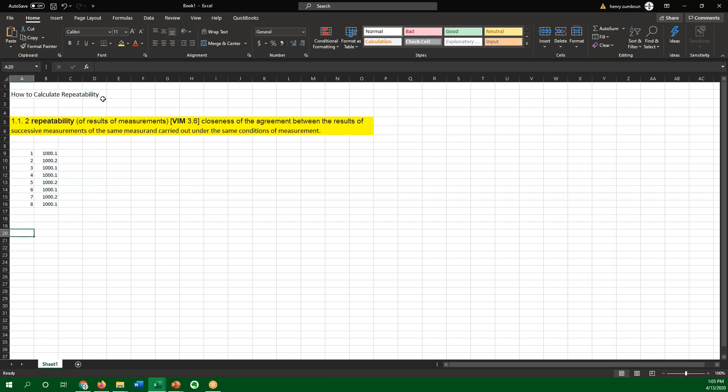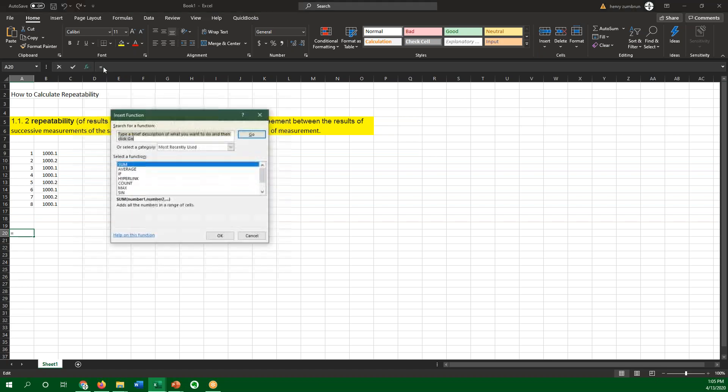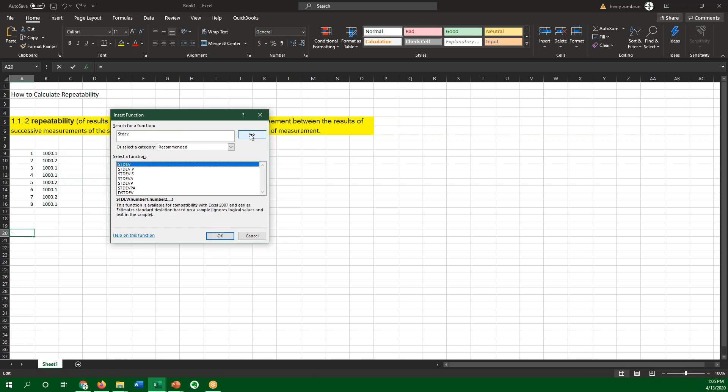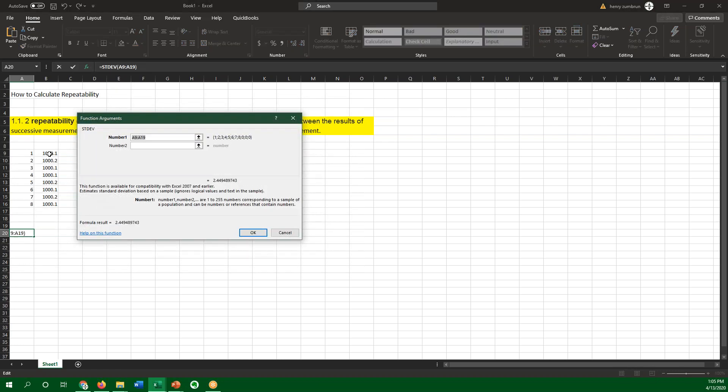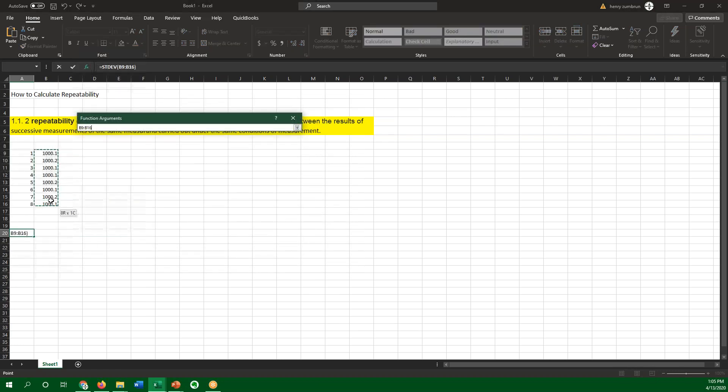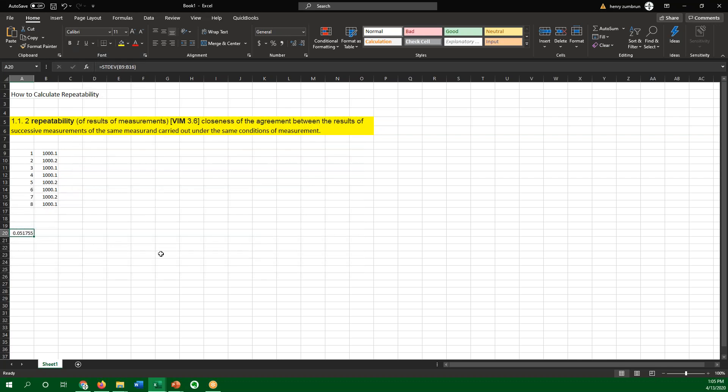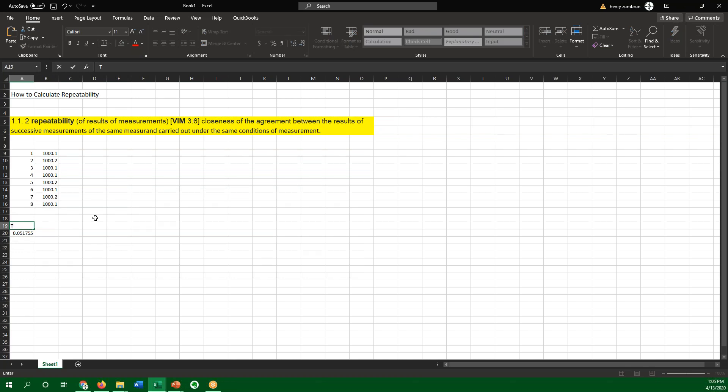And if I wanted to calculate repeatability, what I would really do is just, it's as simple as taking the standard deviation. I'm looking for that. Okay, go function. I want that function. I'm going to grab all these numbers. And effectively, right here, this is going to be my repeatability standard, which is the standard deviation.